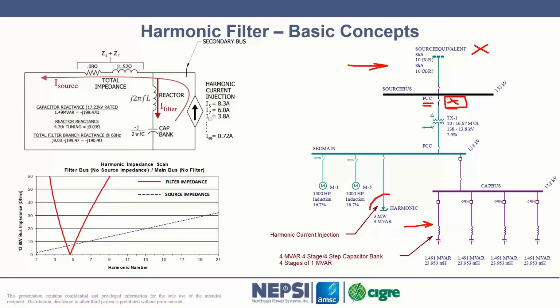I have a harmonic producing device here, and this harmonic producing device is injecting harmonic current. Harmonic current injected from VFD drives and adjustable speed drives, cycloconverters, rectifiers. Remember, those devices are chopping up the current. They create a harmonic current source, which I show over here, and they're injecting harmonic currents. And they're considered an ideal current source, meaning that no matter what my impedance is here, these currents are being injected into this network, okay?